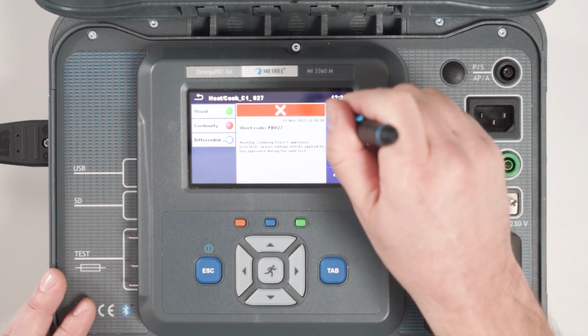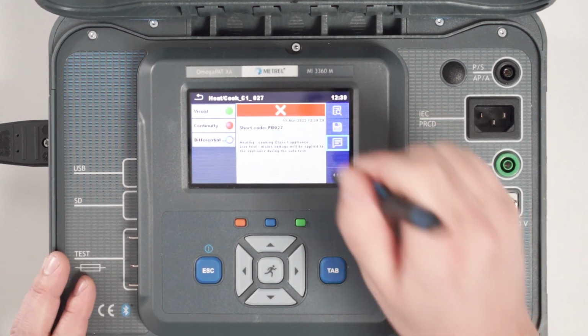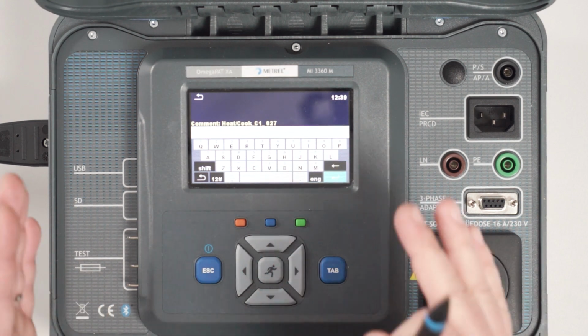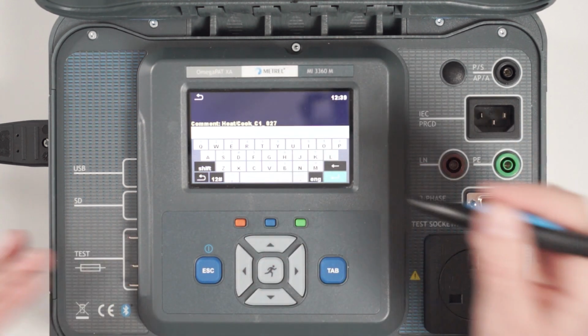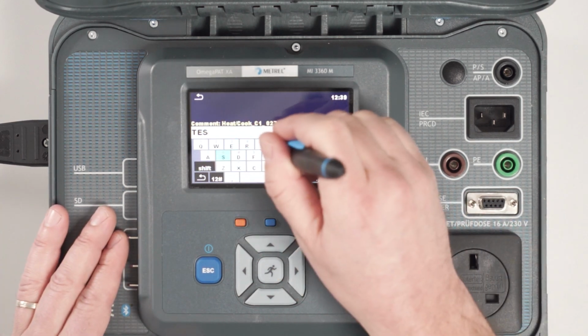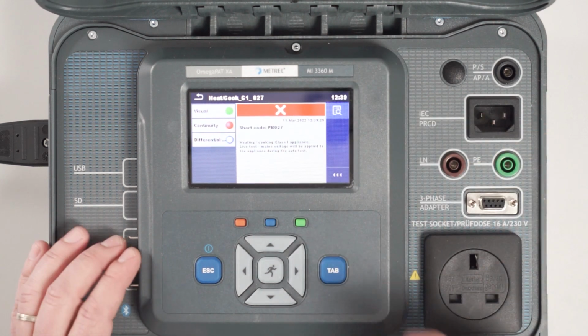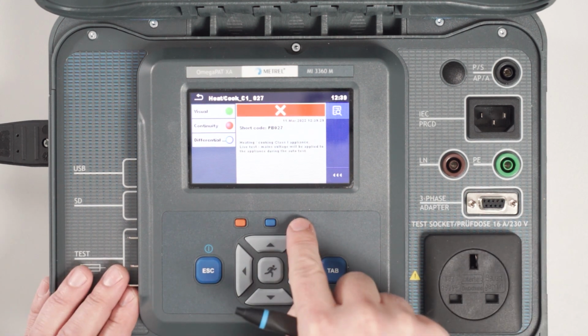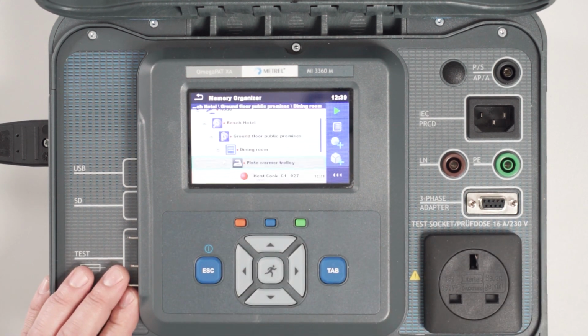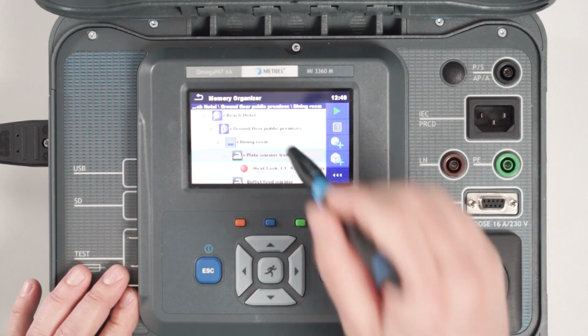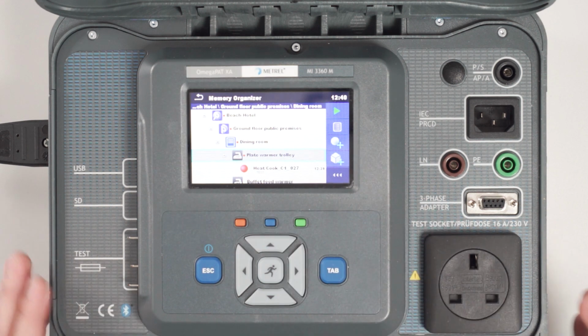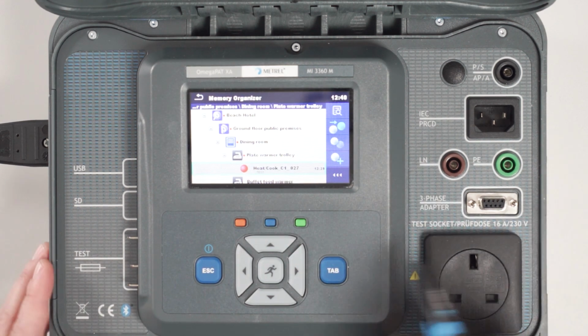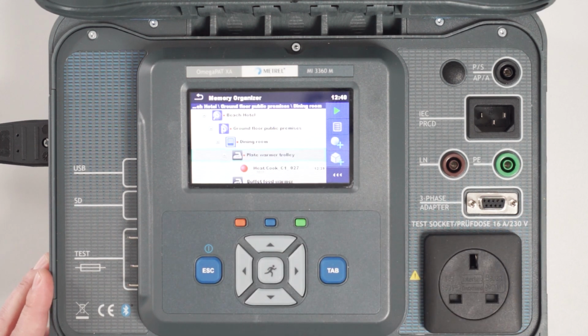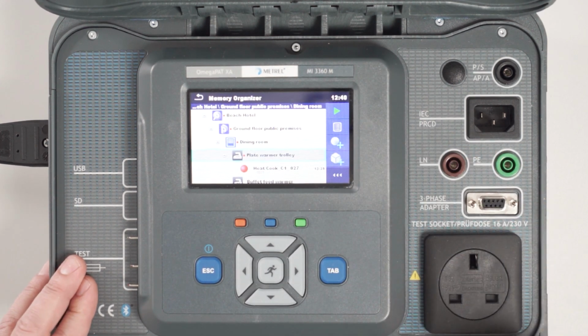We simply stop it. We see the results of this auto sequence here, and we can save it, or we can even comment it. So if we add a comment, this comment will be a part of our auto sequence. So we can say here that this was just a simple test. So test, press enter and save. And now we can jump back into the memory organizer simply by pressing this shortcut button here. So we see that we are in the memory organizer, and under this structure element appliance, we have the test we have just performed, and also what we can see here is the comment of this particular auto sequence.